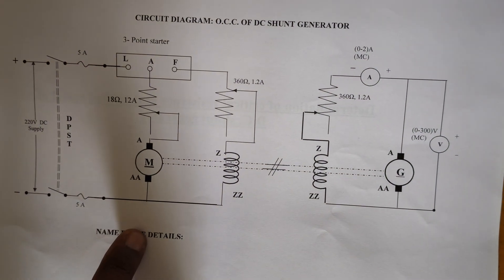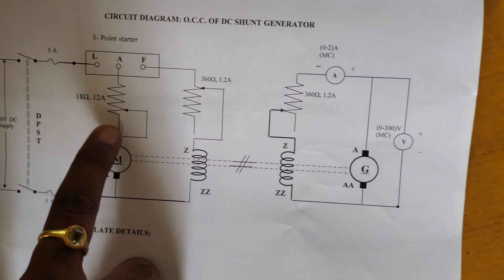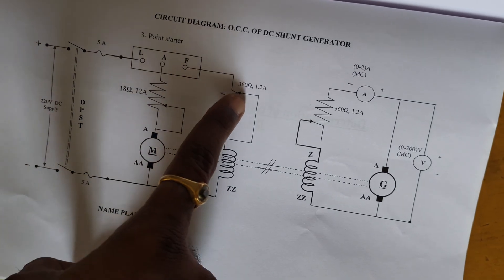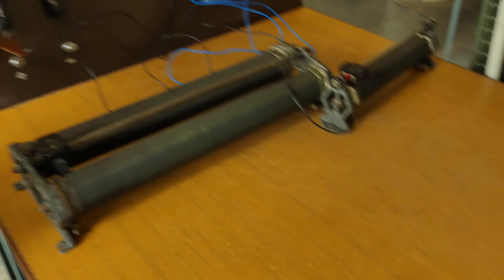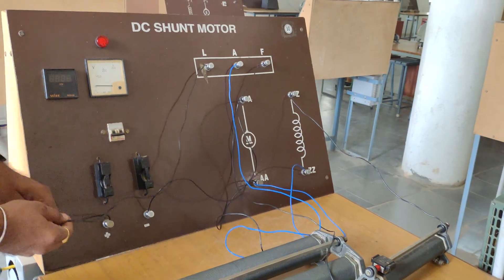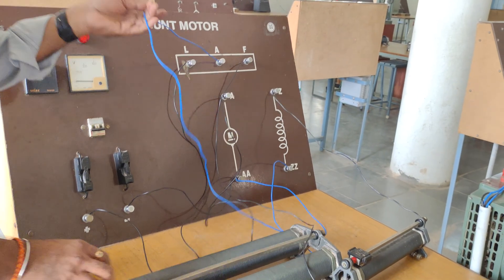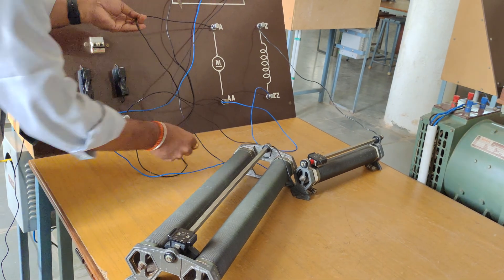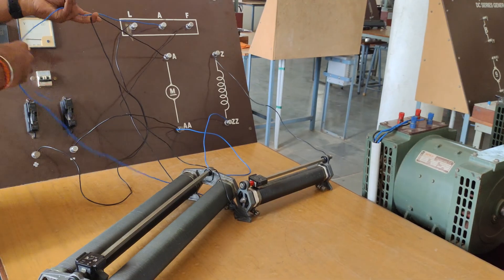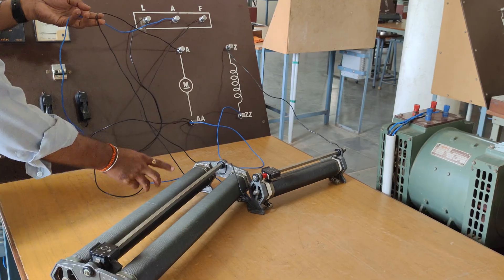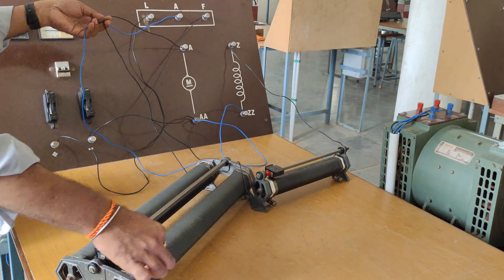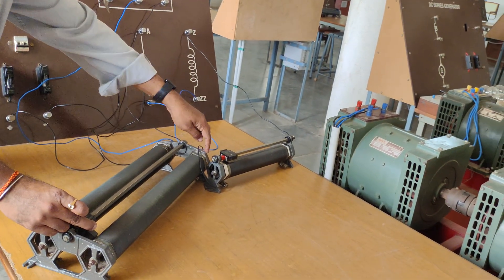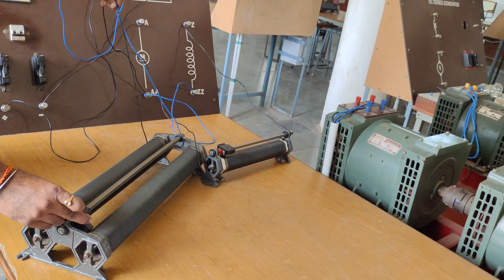Coming to the connections on the motor side, the line is connected to the positive terminal. The armature is connected to one end of the 18 ohms rheostat, and the other armature wire is connected to the other end of the 18 ohms rheostat — this is in the maximum position, meaning the full 18 ohms resistance is in the circuit; current enters here and leaves here. That is why this connection is called the rheostat in maximum position.